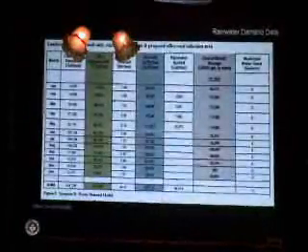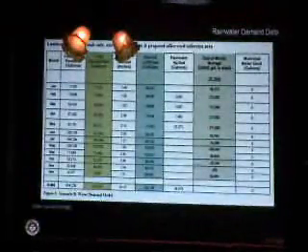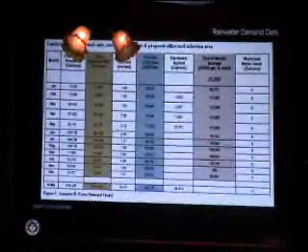We start with 25,000 gallons in storage in the first month. That's assuming that the municipal water supply will fill the storage tanks to 25,000 gallons. And you can see, as the year goes on, in the earlier months, you actually have excess storage, and you're filling the tanks up to 117,000 gallons. At this point, you start to spill. And then in the drier months in the summer, we start to actually use the water that we stored in the tanks. So at the end of the year, you're actually at 60,000 gallons of water, as opposed to the original 25,000 that you started.